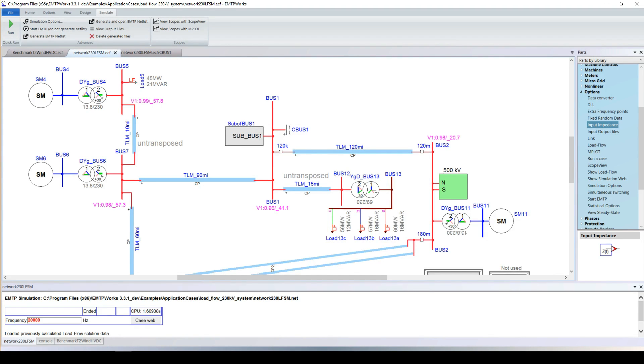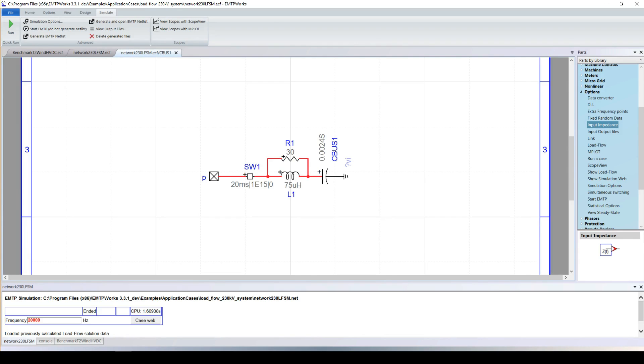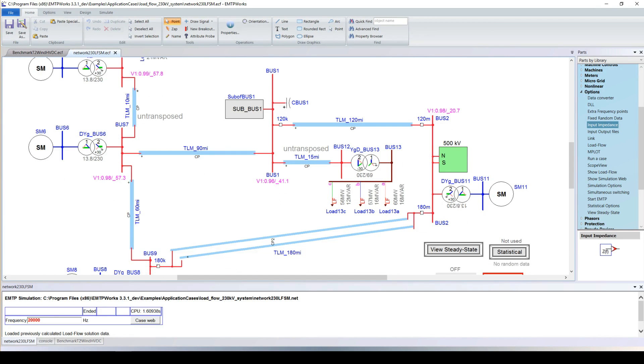When it comes to switching simulations, the switching time is very important. Arbitrarily I connected the capacitor bank at 20 milliseconds, but in a real network — unless the breaker is synchronized — the switching time can be any time: maximum voltage, minimum voltage. The switching can be unbalanced due to material elasticity and viscosity of the breaker, so the three poles never close at exactly the same time. Our goal as engineers is to find the worst overvoltage for insulation coordination. EMTP has built-in capabilities to find the worst overvoltage for a switching case automatically.